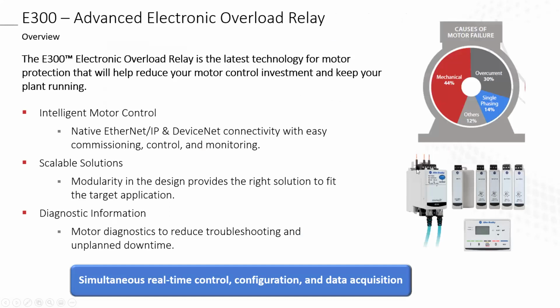So what is the E300? The E300 is the latest technology for motor protection that will help reduce your motor control investment and keep your plant running. E300 has a native Ethernet or DeviceNet communication module, which will allow you to easily commission, control, or maintain your full voltage motor starter using an Add-on Profile. The Add-on Profile is available within Studio 5000.